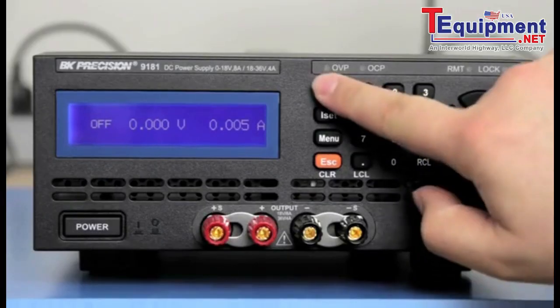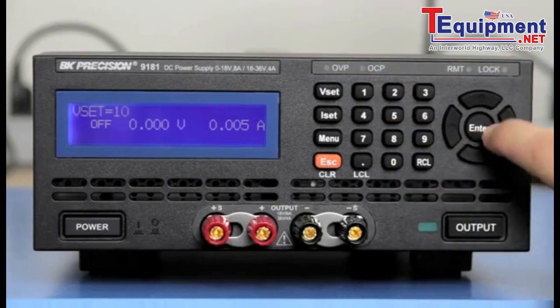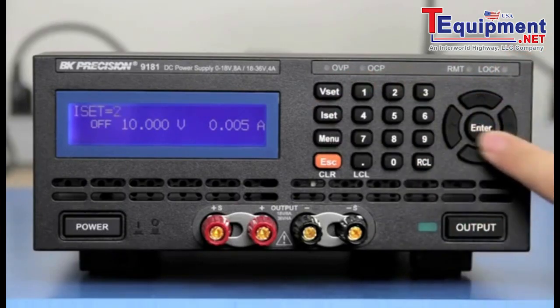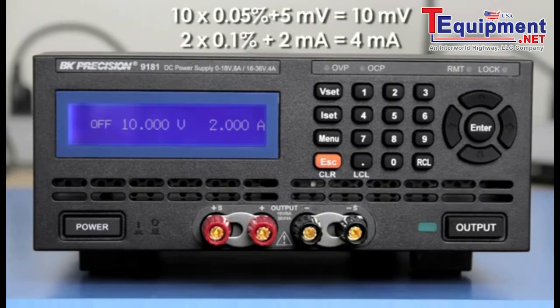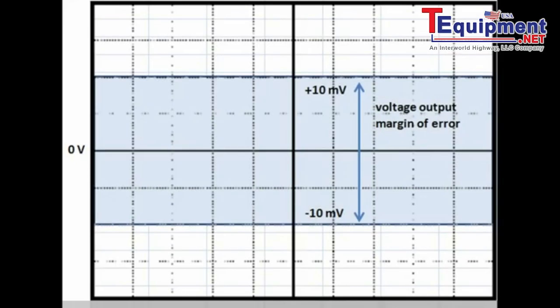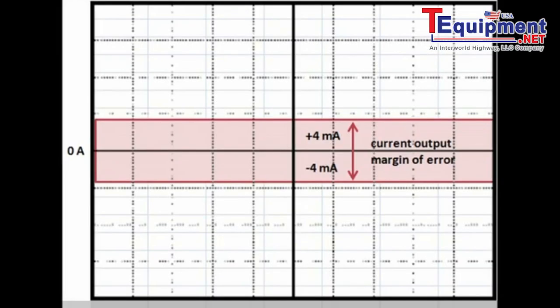So if we set the power supply to 10 volts and 2 amps, the uncertainty of the output would be 10 times 0.05% plus 5 mV, which equals 10 mV, and 2 times 0.1% plus 2 mA, which equals 4 mA. This means the voltage can be off by 10 mV and the current can be off by as much as 4 mA from the actual values.